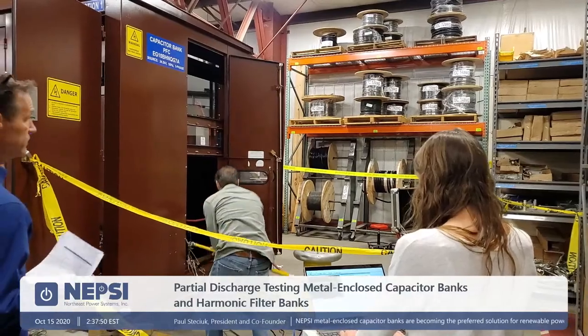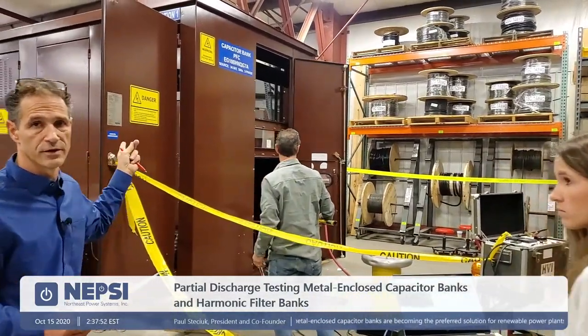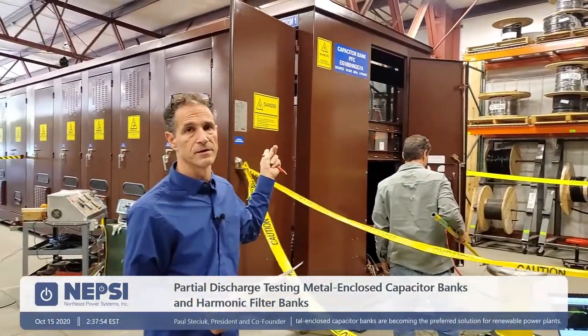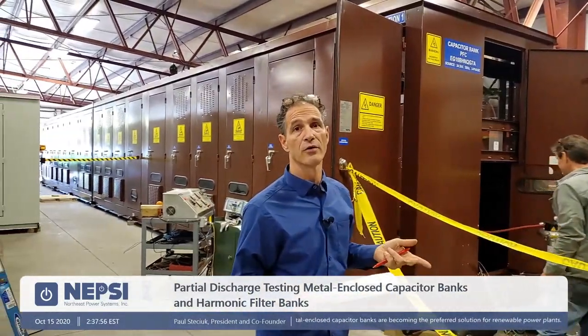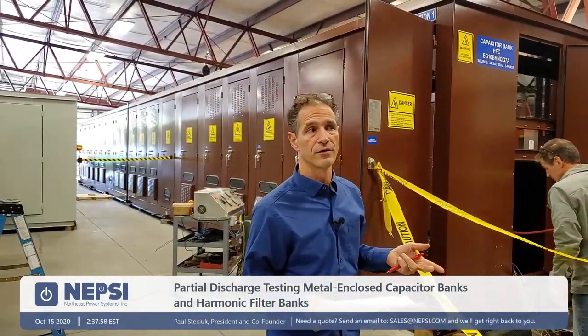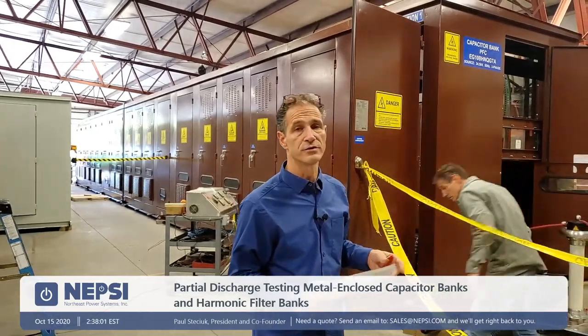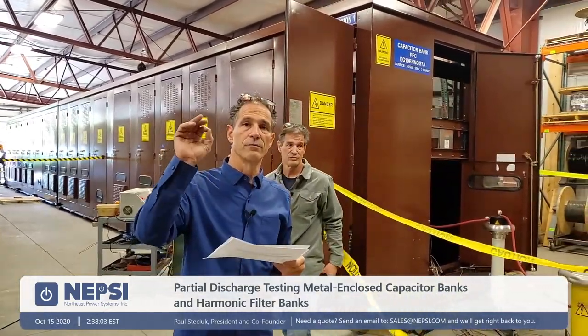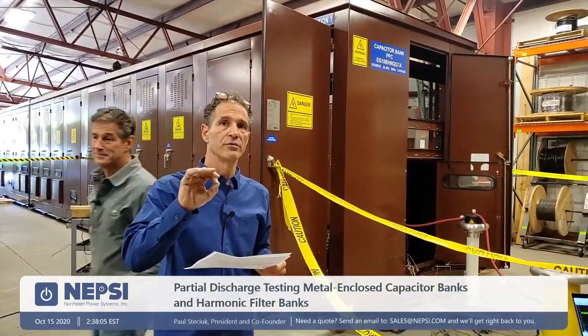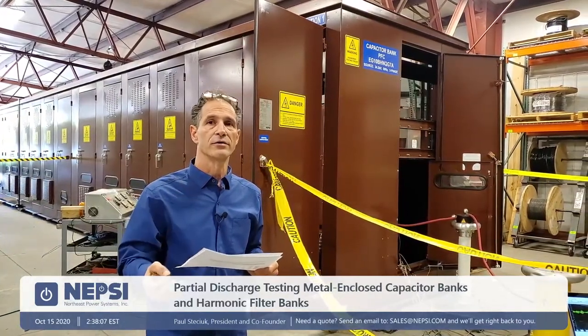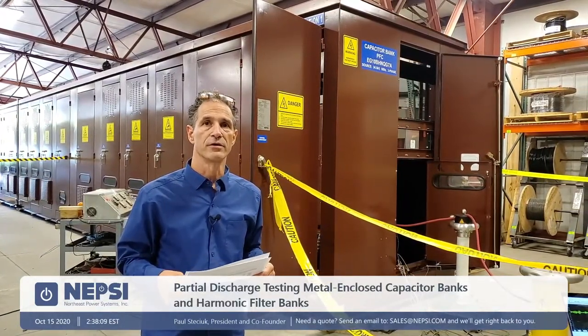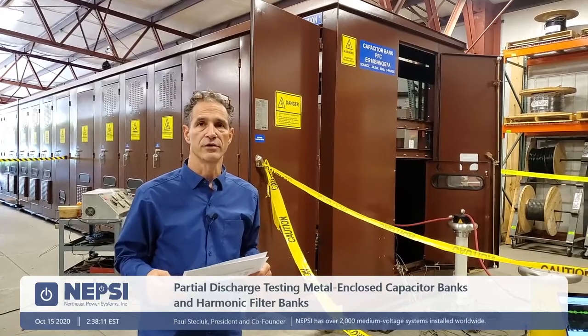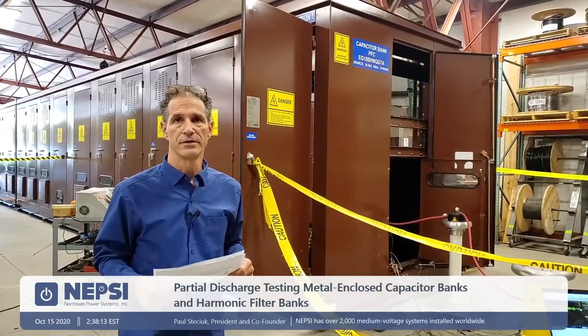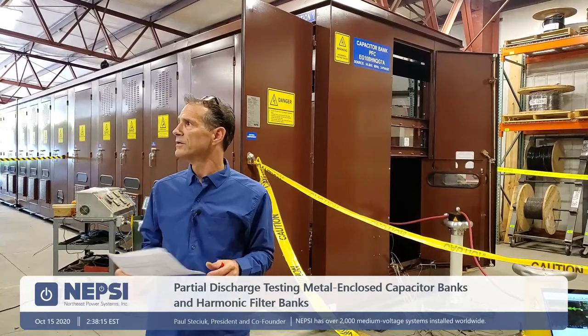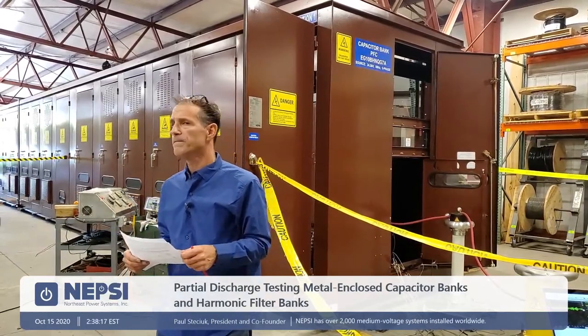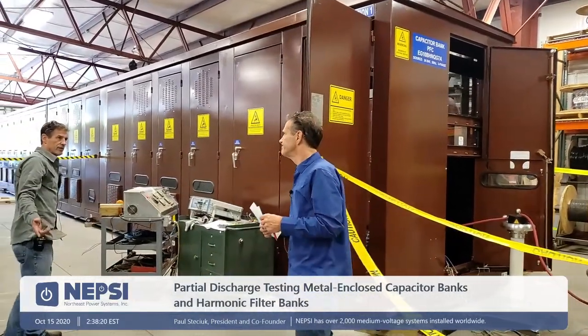So I know for this piece of equipment, I was told just the other day that they did find one issue, and that was an ungrounded breaker. And one of the things with partial discharge is that if you have a piece of metal up by the bus bar somewhere, or anywhere within the equipment, ungrounded metal parts near high voltage parts will definitely result in a failed partial discharge test. What other things have you found? So we found the reactor. You can show the reactor strap.